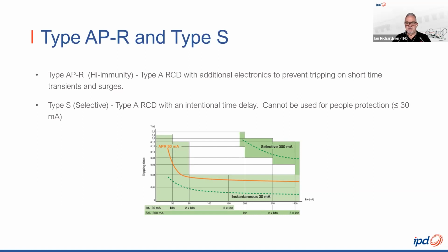The standard requires 30 milliamp RCDs to be an instantaneous operation. However, this is defined by the trip current versus time that we discussed earlier: 300 milliseconds at 30 milliamps, 150 milliseconds at 60 milliamps, and so on. The APR high immunity model still trips under the definition of an instantaneous device. However, they're designed to trip much closer to the upper curve, which provides greater resistance to short-term transients. The APR model can also resist impulses up to 3000 amps, which is just like the type F and the type B.